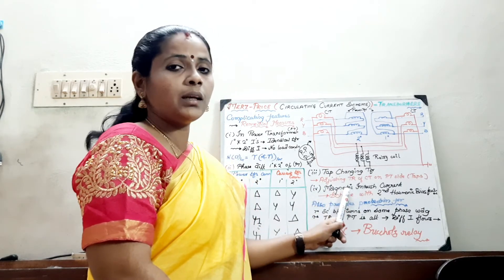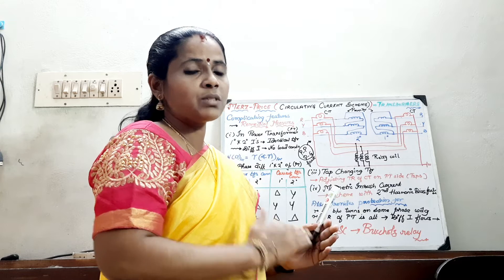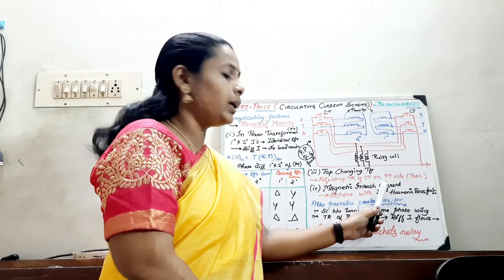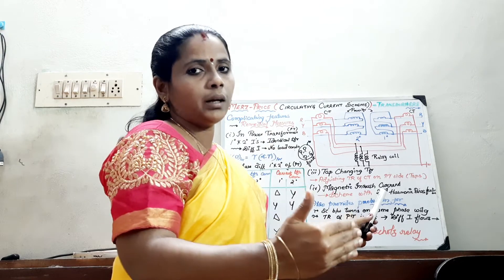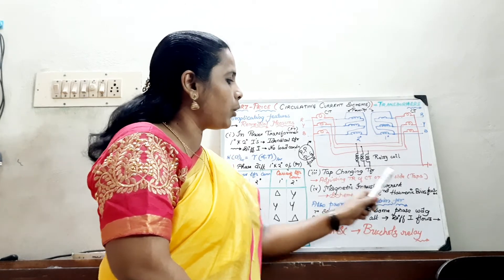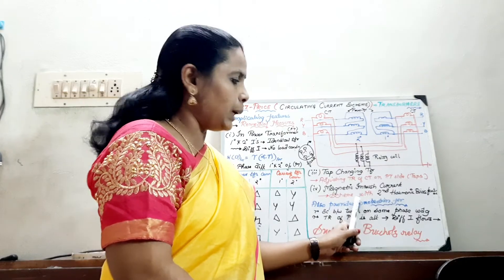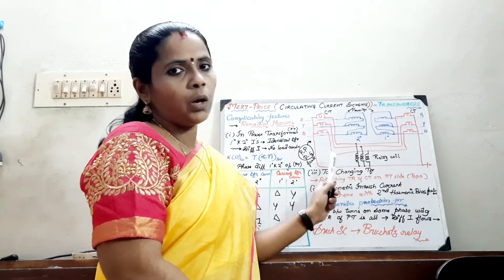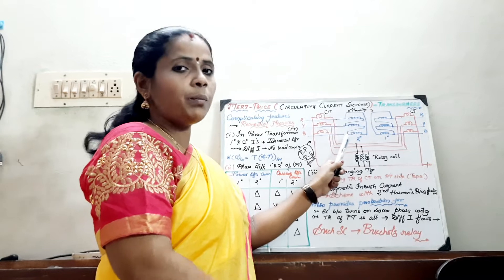The last problem encountered is the magnetic inrush problem. If a transformer has not been in service for a long period of time and is suddenly energized, it results in a magnetic inrush current — the incoming current alone will be of higher magnitude with no outgoing current. In this case, the magnetic inrush problem occurs, and mainly the second harmonic component will be more prominent. To overcome this, we have to devise a scheme that can restrain using the second harmonic bias feature, so that this problem will be avoided. Once all these measures are provided, the transformer protection will be ready.